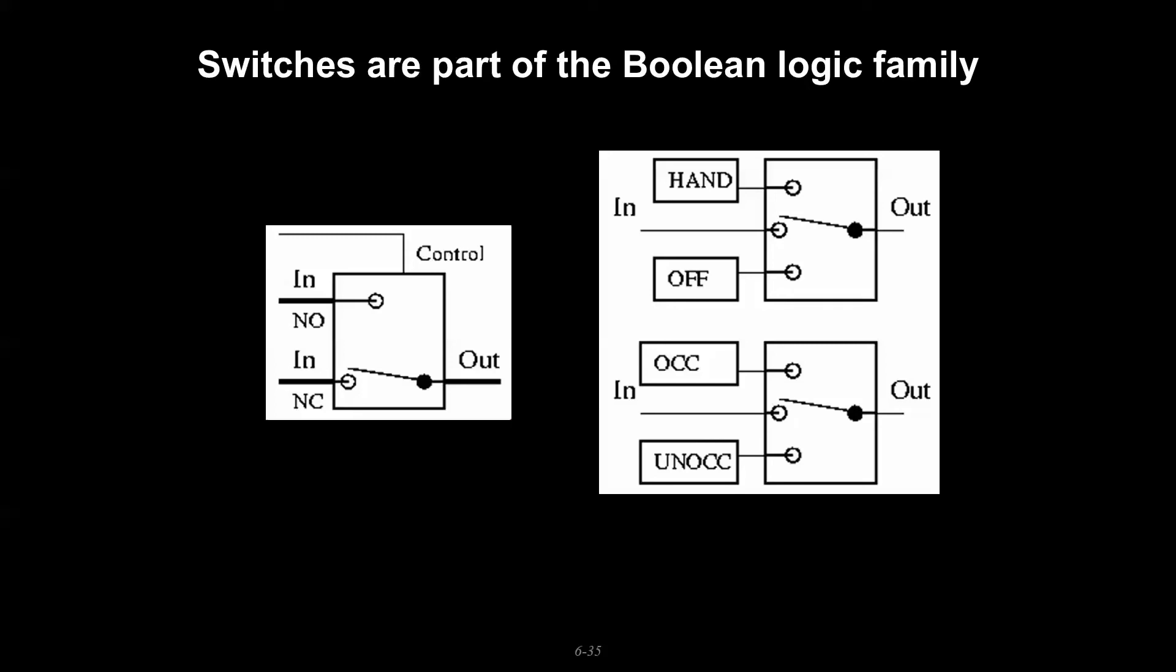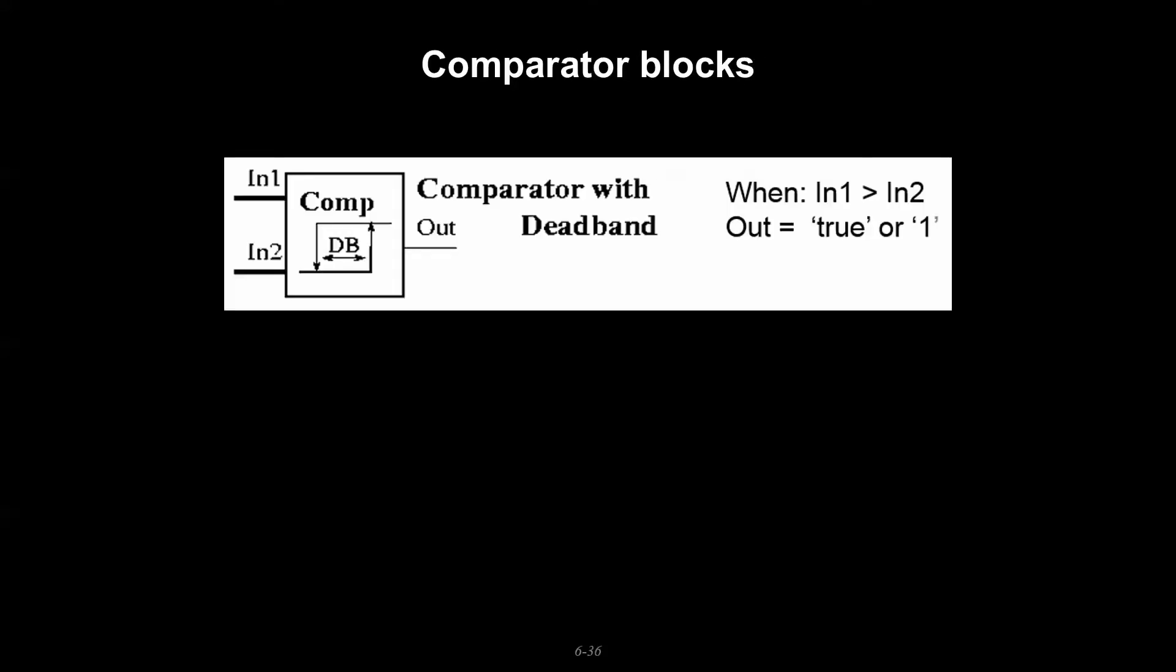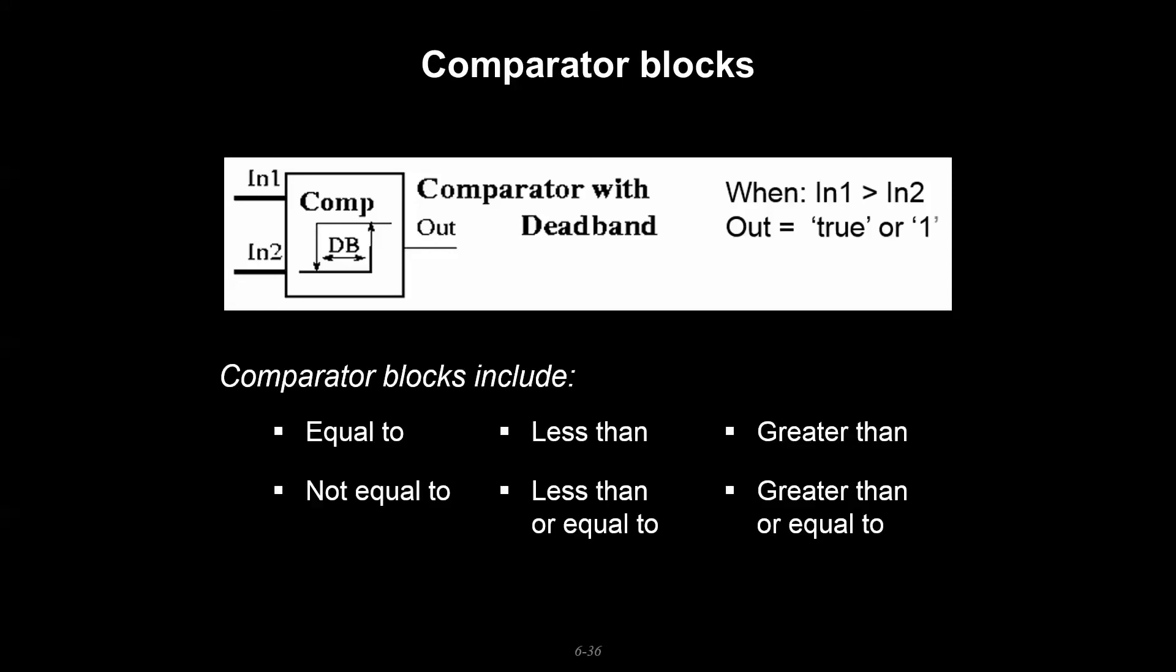Comparator blocks can be important as well, where you have two analog values coming to this comparator block, and if they meet the condition within the dead band prescribed, then you would pass a one through rather than a zero. There's different flavors this may take on and they all have something to do with being equal or less than or greater than or some combination of that.